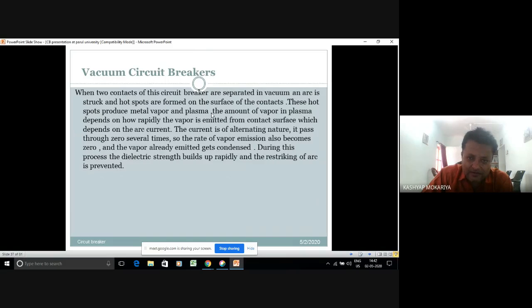Vacuum circuit breaker. Most diploma engineers, degree engineers, masters engineers, and the engineers who joined the industry after their masters will immediately face this breaker, the vacuum circuit breaker. When two contacts of the circuit breaker are separated in vacuum, an arc is struck and hotspots are formed on the surface of the contacts. These hotspots produce metal vapor and plasma. The amount of vapor in the plasma depends on how rapidly the vapor is emitted from the contact surface, which depends on the arc current.